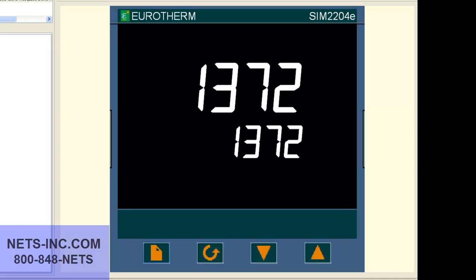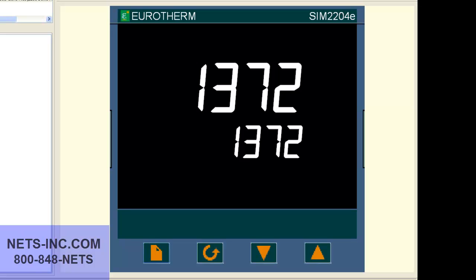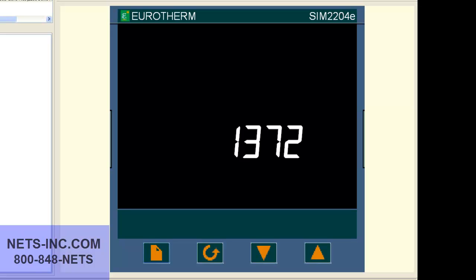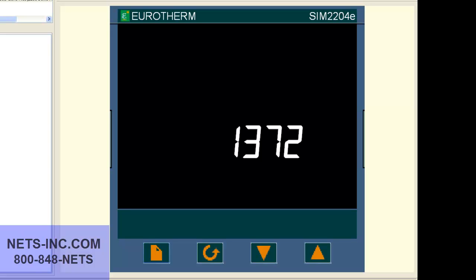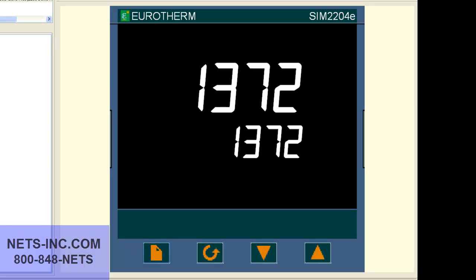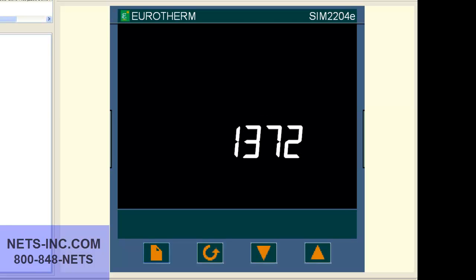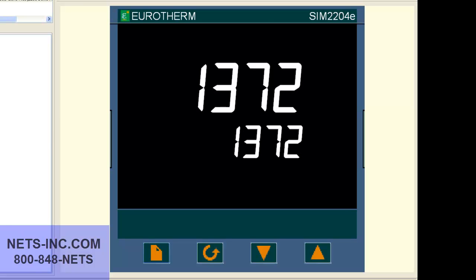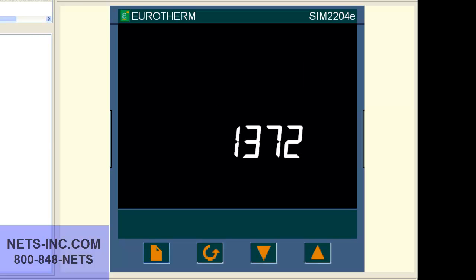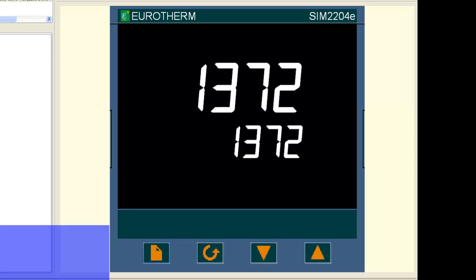On a Eurotherm 2200 series controller, the controller is set up as PID control with control action set as reverse for a typical heating application. We are going to change the control action from reverse to direct for a typical refrigeration cooling application.